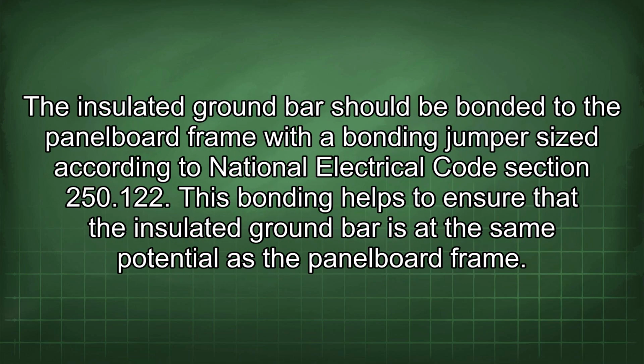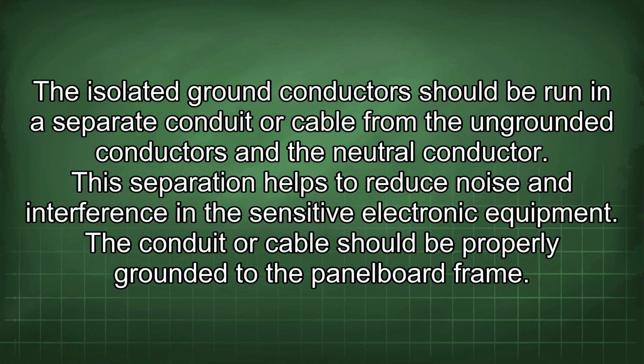The insulated ground bar should be bonded to the panel board frame with a bonding jumper sized according to National Electrical Code Section 250.122. This bonding helps to ensure that the insulated ground bar is at the same potential as the panel board frame. The isolated ground conductor should be run in a separate conduit or cable from the ungrounded conductors and the neutral conductor. This separation helps to reduce noise and interference in the sensitive electronic equipment.